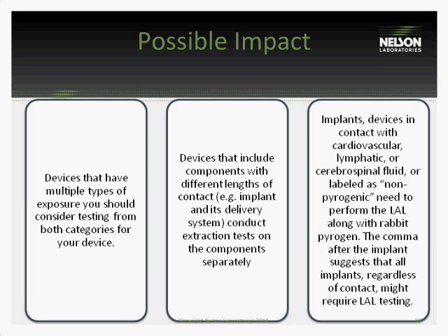So the first one is that devices that have multiple types of exposure should consider testing from both categories for your device. Now, an example off the top of my head for this one is that if you have, let's say, a drug delivery device or even an IV bag, for example, and you have some kind of port that's left in the patient that might have different devices going through, and that port is implanted long term, but the devices have short-term contact, then you have to evaluate both categories of your device.